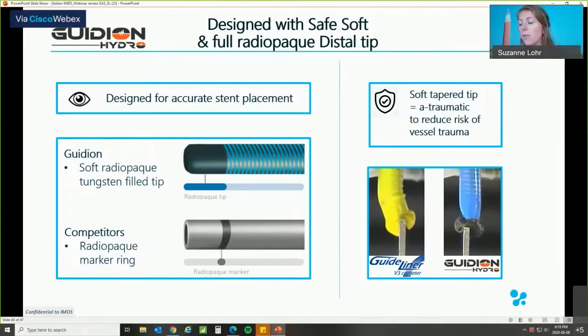The tip of the Guidion is fully filled with tungsten, so it's visible completely on the angio, and you know exactly where the distal end of the guide extension is. So when you're placing a stent and you want to expand the balloon, you know exactly where you can expand it, and you don't have any risk of expanding inside a guide extension. Looking at the competitors, as also told before by Dr. Gasparini, they all have a radio-opaque metal marker ring. Since this marker ring is very stiff and sharp, it's not possible to place it at the very distal end of the tip of a guide extension. So you always have to take into account a few millimeters before you really know where the distal end of your guide extension is.